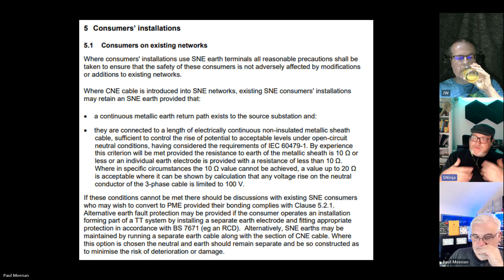Mate, when I went to Eddie's issue at his church, they didn't have a clue what we were talking about. I had to get one of our YouTube webinars up on my phone and show them. And they were looking at it going, oh, yeah, I recognise that. And I had to go through their standards with them. The field guys don't read these standards. They read their UKPN work instructions or their RAMs. They don't read this stuff. So it then carries on and says alternative fault protection may be provided if the consumer operates an installation forming part of a TT by installing a separate earth electrode.